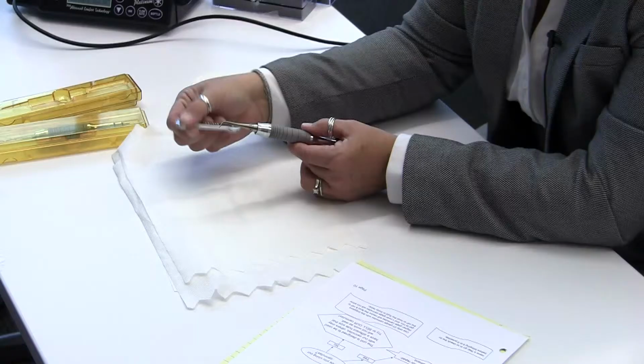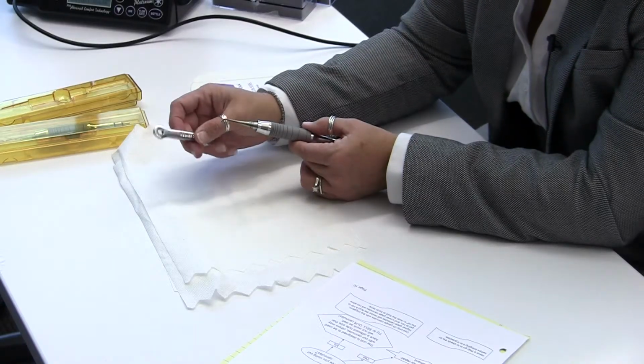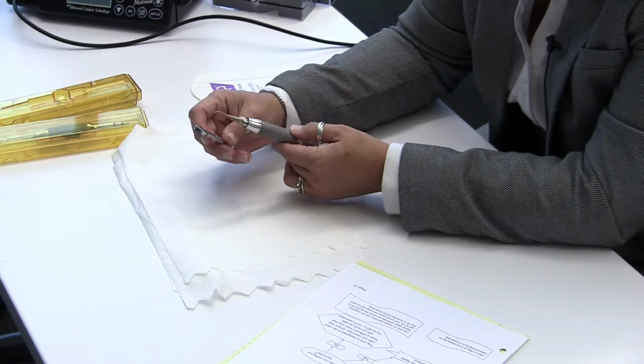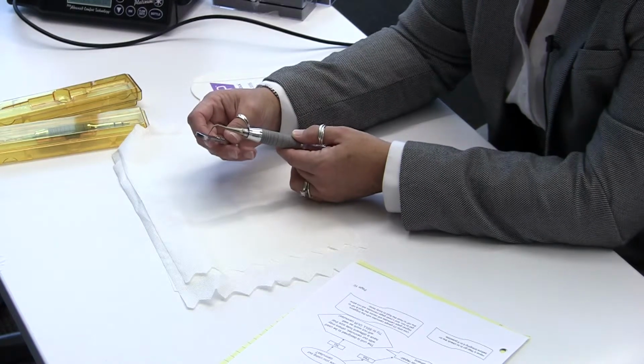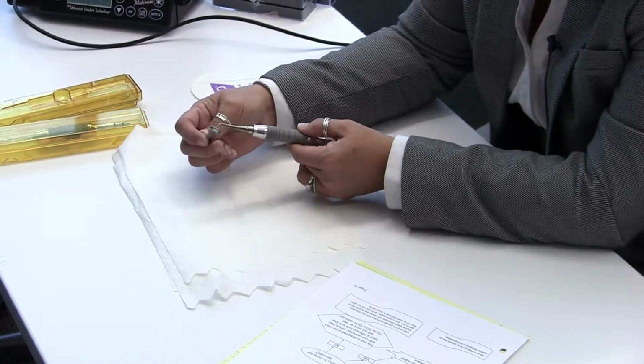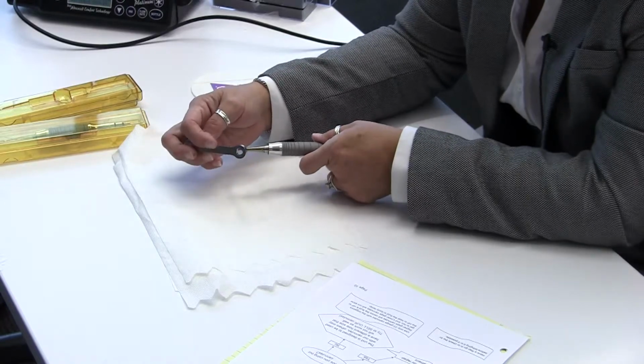You're not getting any mist from your handpiece. The first thing we need to check is this handpiece itself, is this tip a good tip? In other words, what I'm asking you is, on your wrench that you received with your unit, you're going to be able to notice that there's a little hole that's underneath where you would tighten the tip. We want to make certain that when we put the tip through the hole, we can see it through the other side. If we can't see it through the other side, it means that the water may not be hitting the tip. It is vibrating, but the water is not hitting the tip to create that mist.